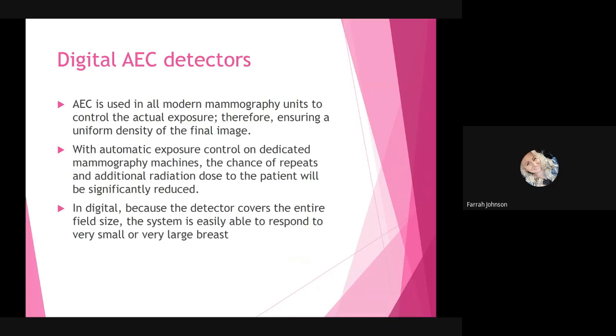So, digital AEC detectors, just like an X-ray. AEC is used in all modern mammography units, and that's to control the actual exposure, therefore ensuring a uniform density of the final image. Now, with automatic exposure control on dedicated mammography machines, the chance of repeats and additional radiation exposure dose to the patient will be significantly reduced. Note that in digital, because the detector covers the entire field size, the system is easily able to respond to a very small or a very large breast.